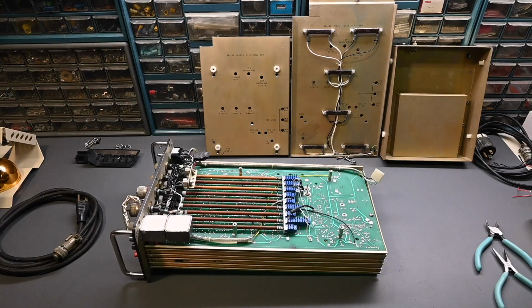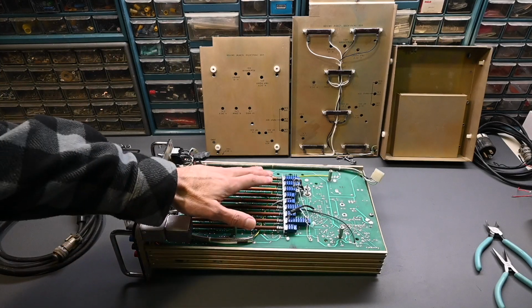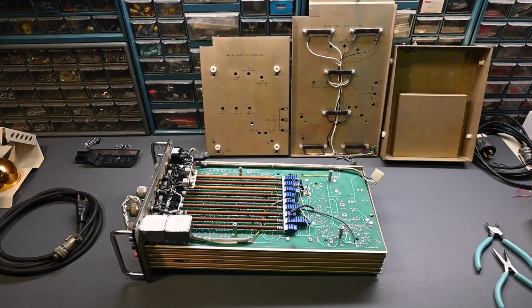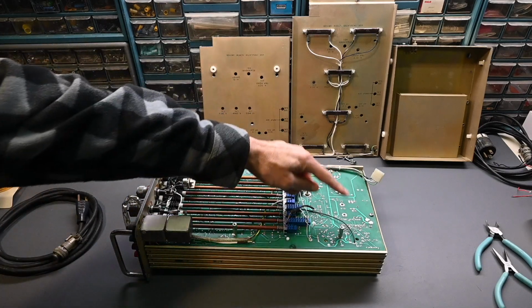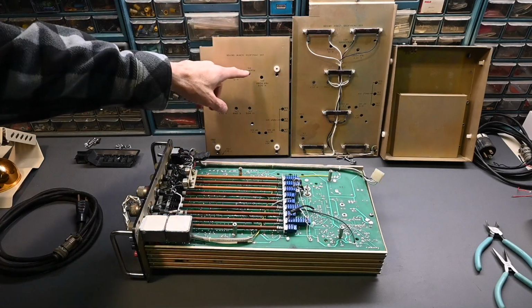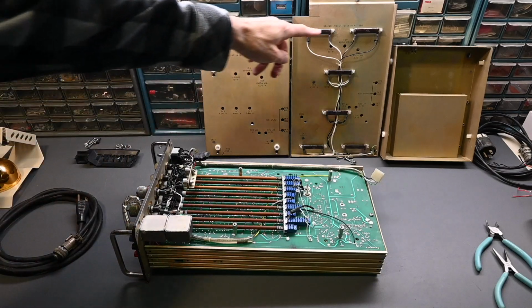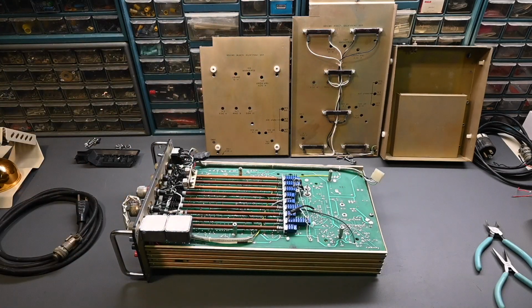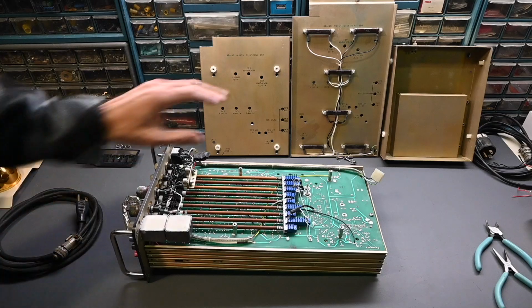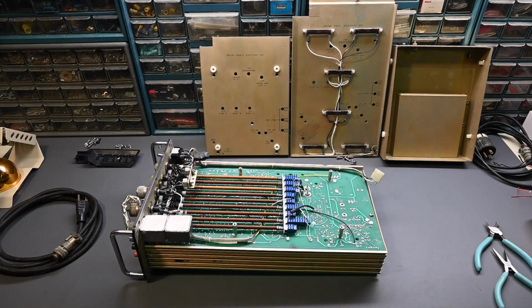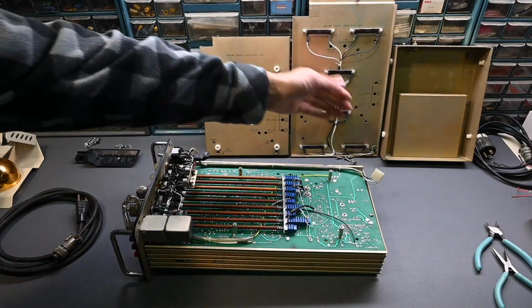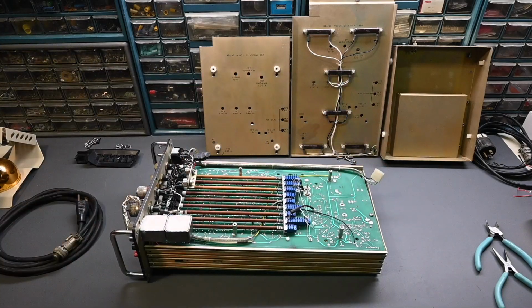I disassembled the multimeter a little further so I can inspect the bottom of the circuit board before trying to power up the instrument. This panel fits on these four standoffs, and then this panel fits on top of that one. These six power resistors are just used to heat the instrument if it falls down to freezing temperature, so I can leave all of this disconnected—it won't have any effect on powering up the instrument. This panel plugs into this connector right here.